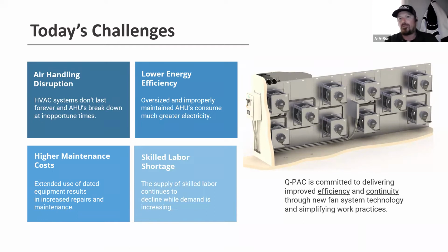So a lot of the challenges that we run across today for contractors and clients are air handler disruptions, low energy efficiency of their systems, higher maintenance costs associated with bearings, belts, just replacement costs, as well as the skilled labor shortage of finding people to work on some of these systems that are still in place 30, 40 years in their lifespan. The Q-PAC system delivers a higher efficiency with EC technology, as well as continuity across an entire building. So we can use, instead of maybe 4 or 5 different motors, 1 or 2, or maybe 3 different size fans for an entire building, which allows the customer to have quite a few less replacement parts in the long run.